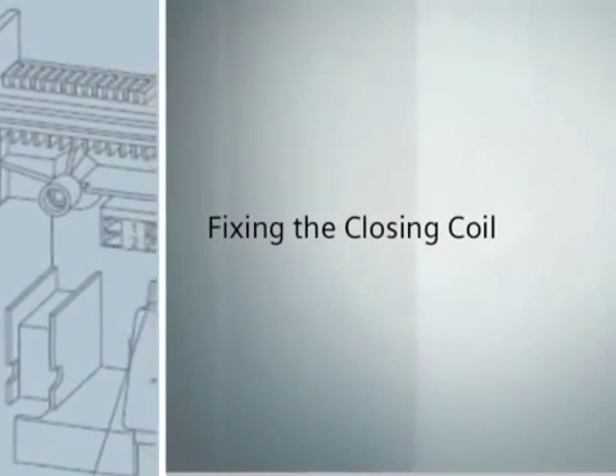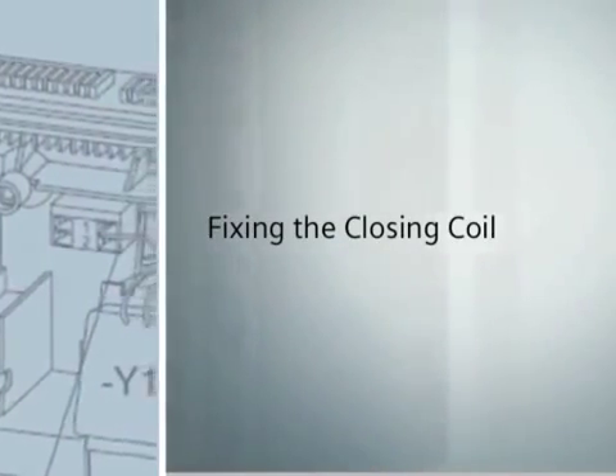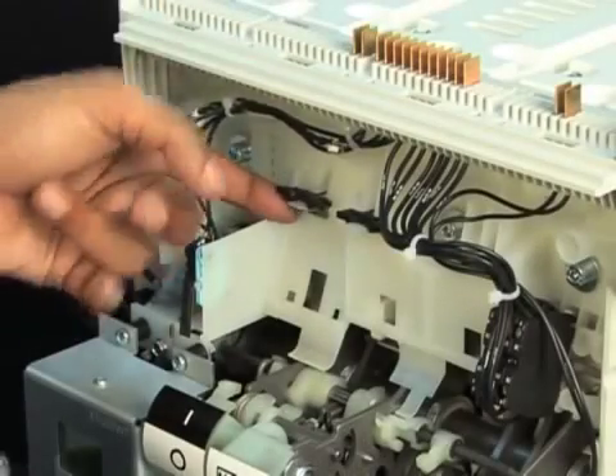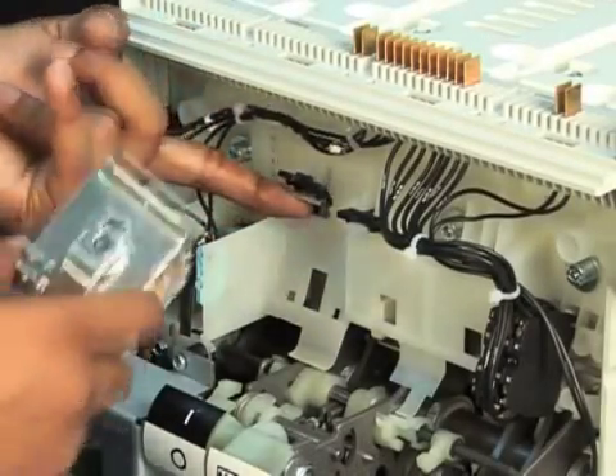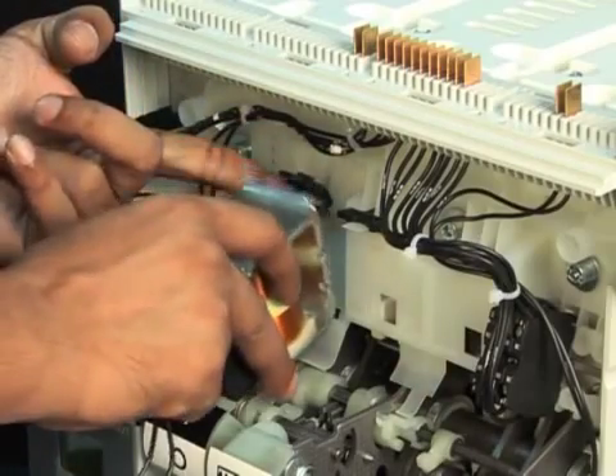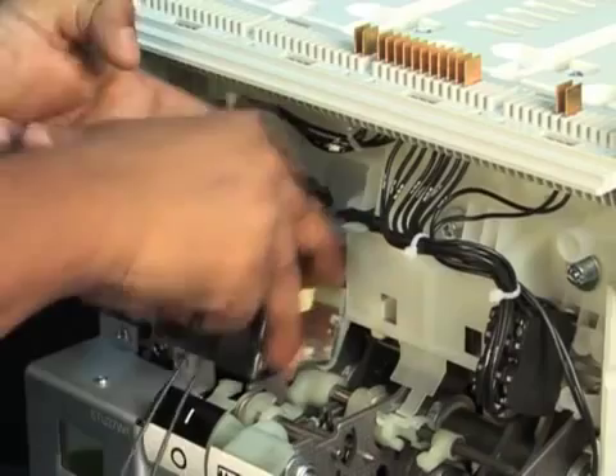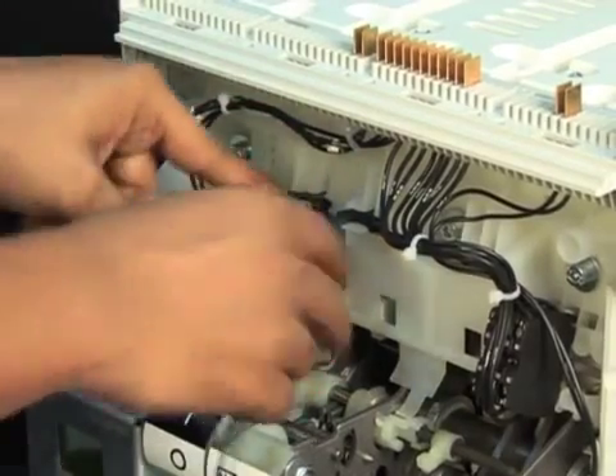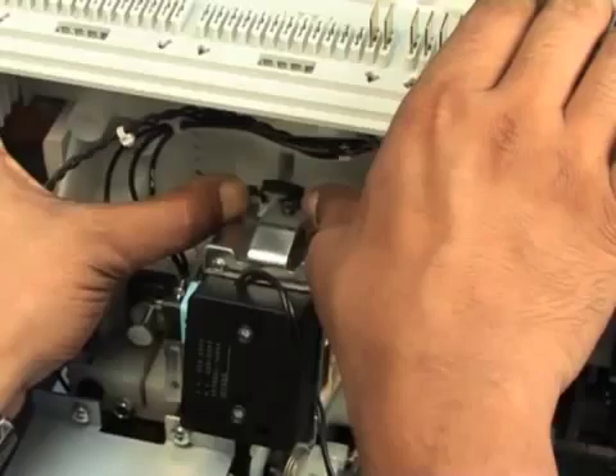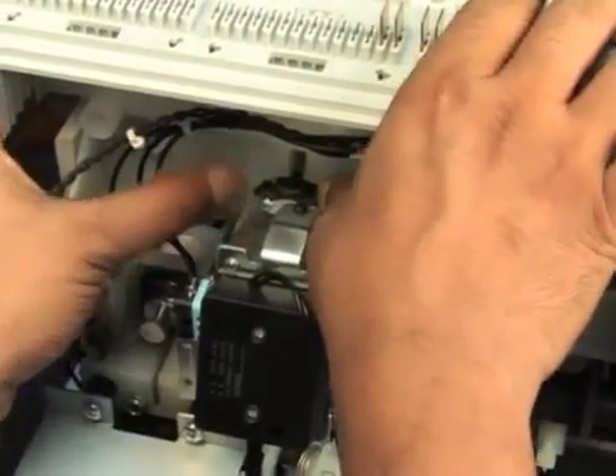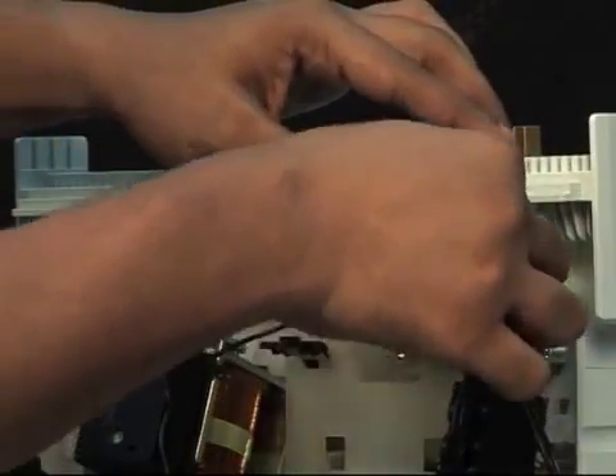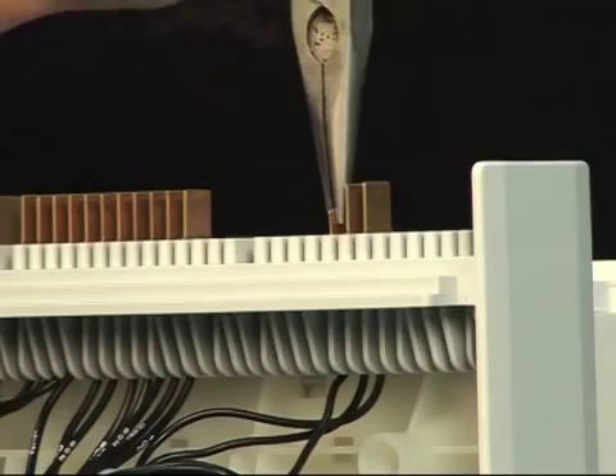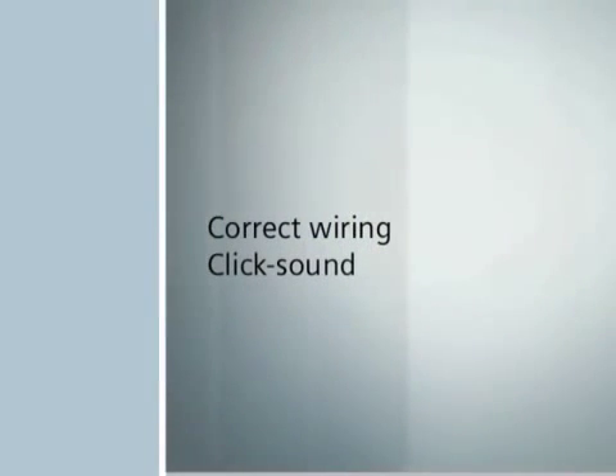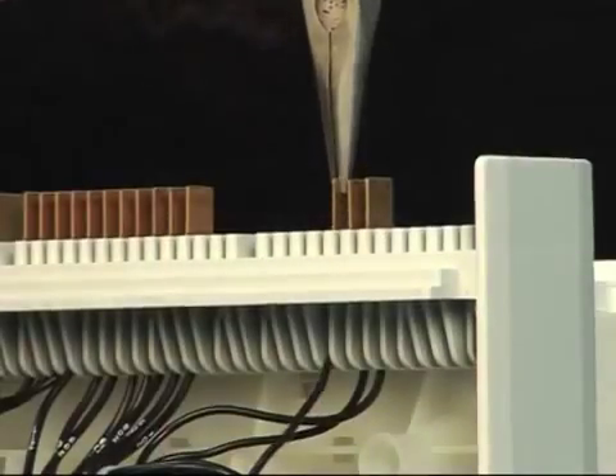Next, we shall fix the closing coil on the extreme left slot. You have to pull the black colored plastic bolt and incline the coil towards the front to insert the bracket behind the coil into the white groove on the breaker's inside wall and click fit the top of the back plate below the hook. Then, press the bolt back gently to its original position till it has no movement. Please insert the blade contacts in X112 and X111. The fixing of the blade contacts at the terminals should be ensured with the fitment sound.